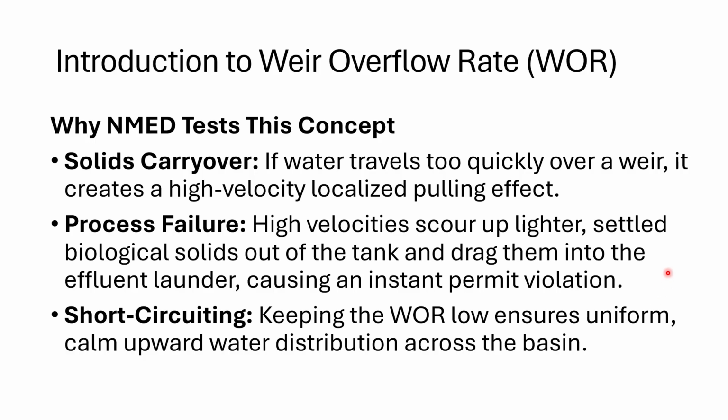And those higher velocities, if they're too high for the exit velocity of the wastewater leaving that clarifier, they can scour up the top of the sludge blanket, which is composed of lighter biological solids that just settled out, and drag them into the effluent launderer. And if it's in the secondary clarifier, you're going to have an instant permit violation because you're going to be discharging solids, and you don't want that.